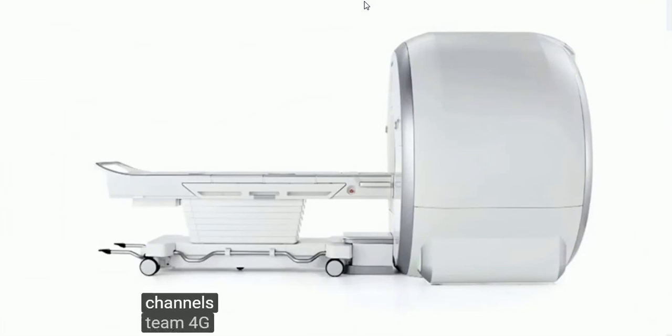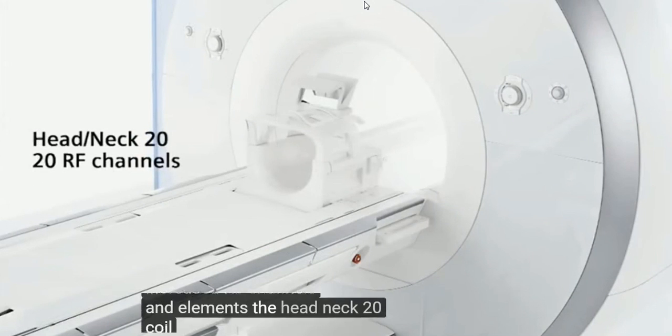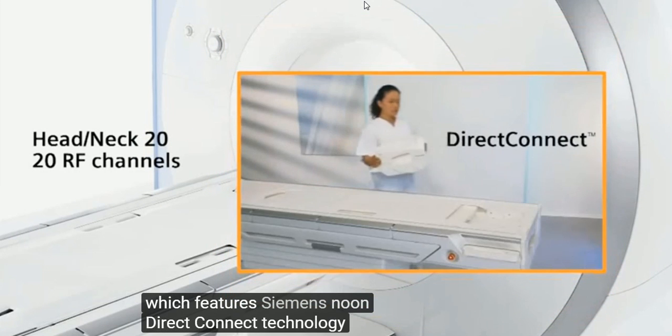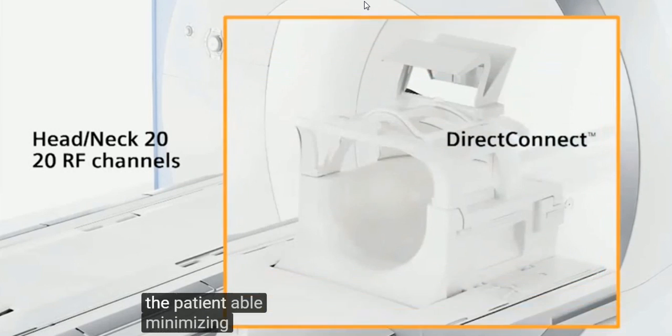TIM4G also introduces a whole new set of ultra-high-density coils with increased RF channels and elements. The Head/Neck 20 coil features Siemens' new DIRECT CONNECT technology. DIRECT CONNECT coils are cable-less, plugged directly into the patient table, minimizing set-up time and increasing signal-to-noise.